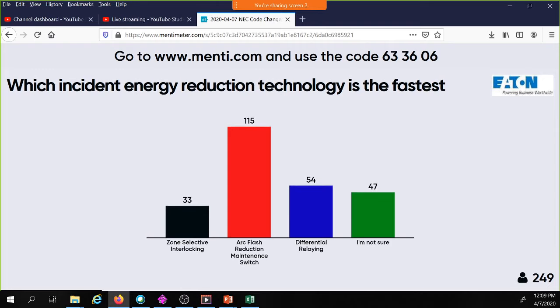The arc reduction maintenance switch is faster than instantaneous, so it's faster than 2 cycles. And remember, 1 cycle is 0.0166 whatever seconds. So the arc reduction maintenance switch is the fastest solution on there. And that's why it's important to be in the class on Thursday to understand how overcurrent protective devices work, because that will help you completely have the fundamentals to understand why some technologies react faster than others.